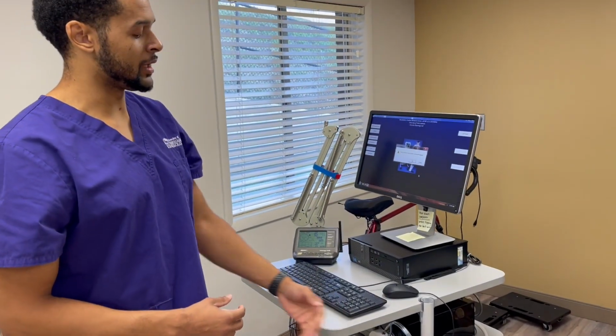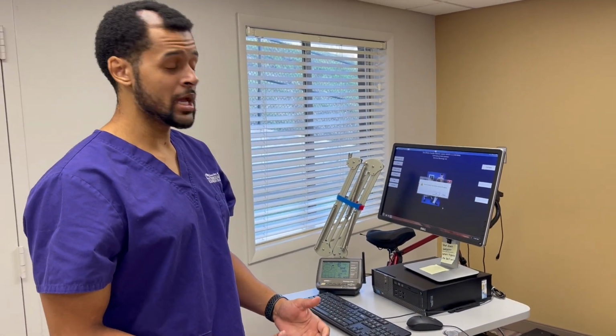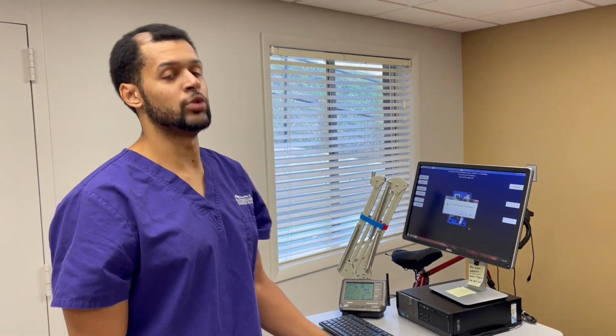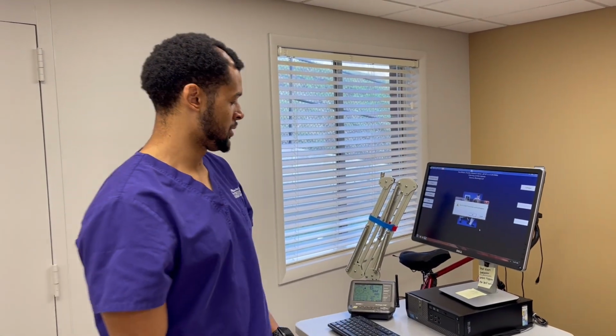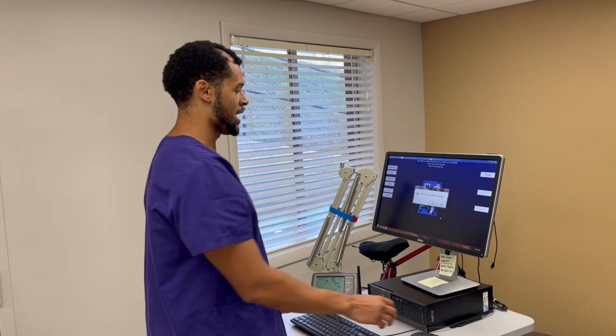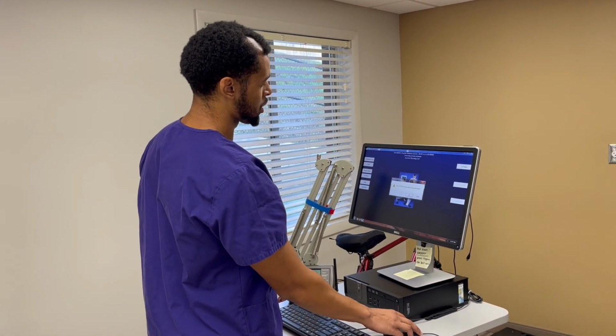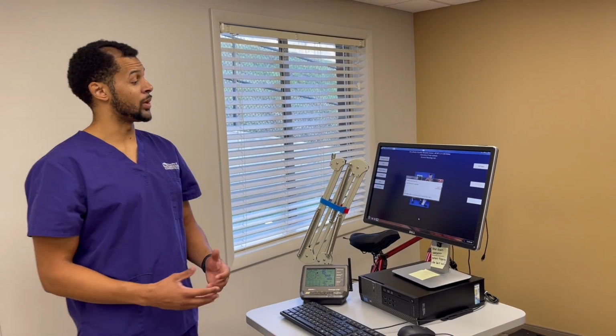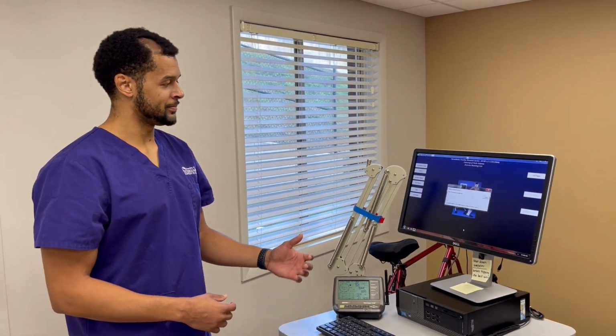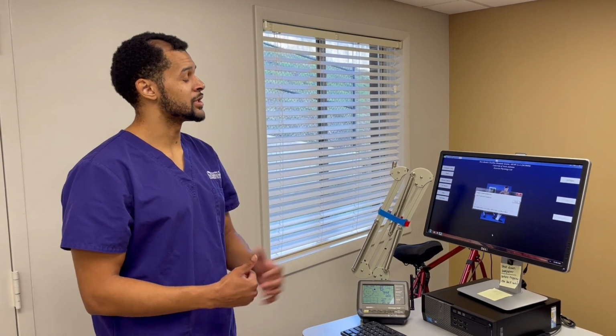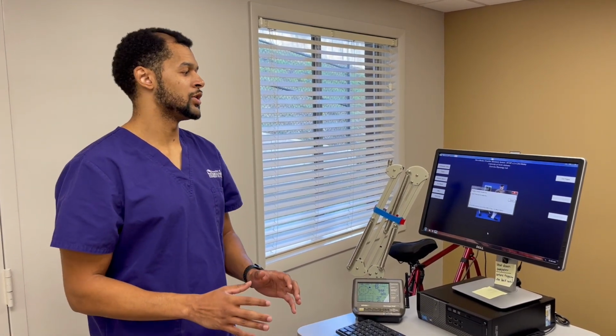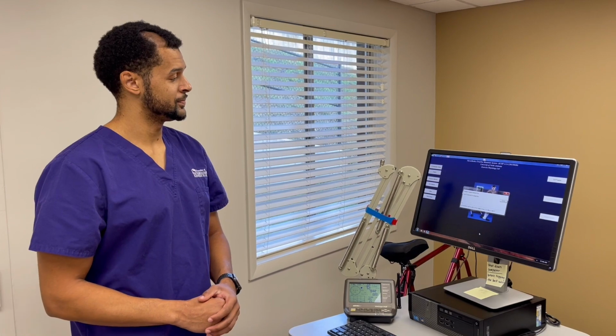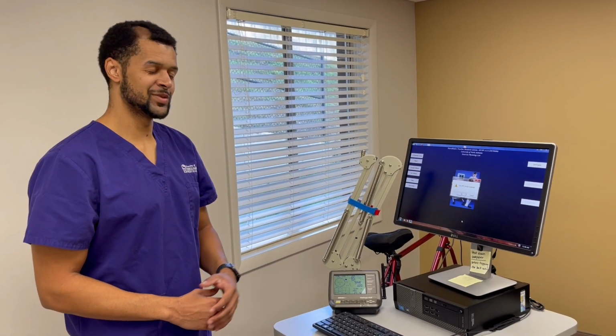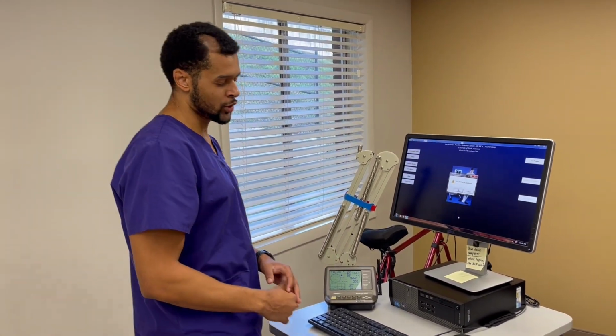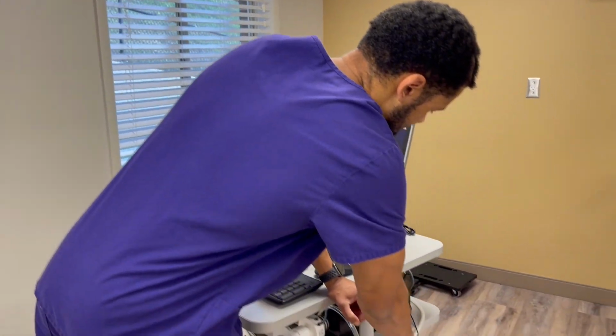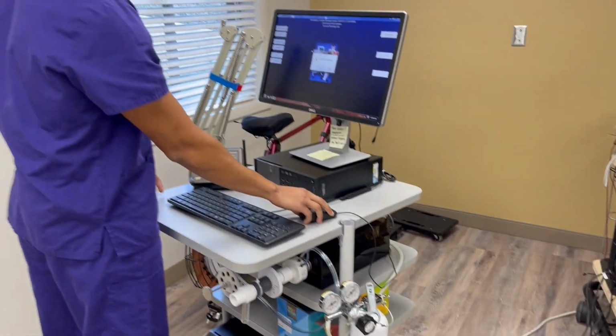You want to make sure that the gas is set to 3 psi. Normally it should be set to 3 psi and you do not have to move or adjust it. And make sure it never goes above 5 psi. So once you turn it counterclockwise to 3 psi, you'll hit OK, and then it will calibrate. It will take about 10 to 11 seconds to calibrate, so if it's taking a while, it is okay, it is still working. Okay, so once it is off, then you're going to turn off the gas cal and hit OK.